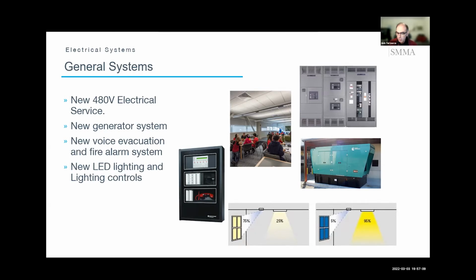As Lana alluded to, because we have an all-electric system, as you start adding load like that to a generator, electric heat adds quite a bit of load to the generator system. So right now our base system is about 350 kW, which is kind of that minimal system, freeze protection, coolers, freezers, that kind of thing. But there's plenty of time to discuss whether there are other parts of the occupiable building you'd like to back up.